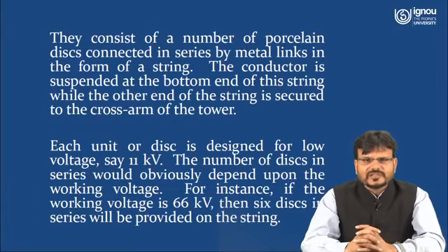They consist of a number of porcelain discs connected in series by metal links in the form of a string. The conductor is suspended at the bottom end of the string while the other end of the string is secured to the cross arm of the tower. Each unit or disc is designed for a low voltage, say 11 kV, as I already discussed. The number of discs in series would obviously depend upon the working voltage.